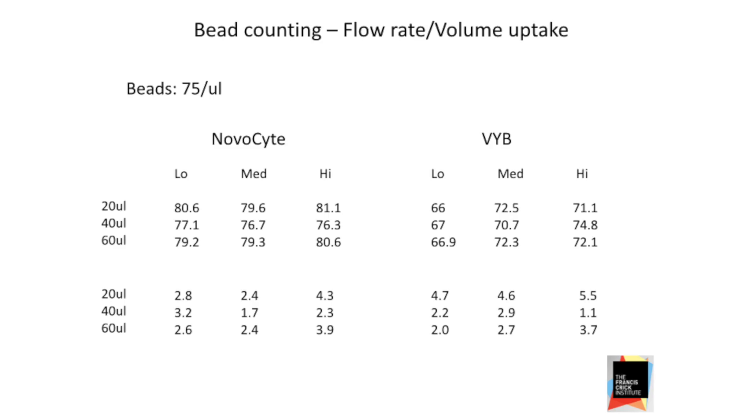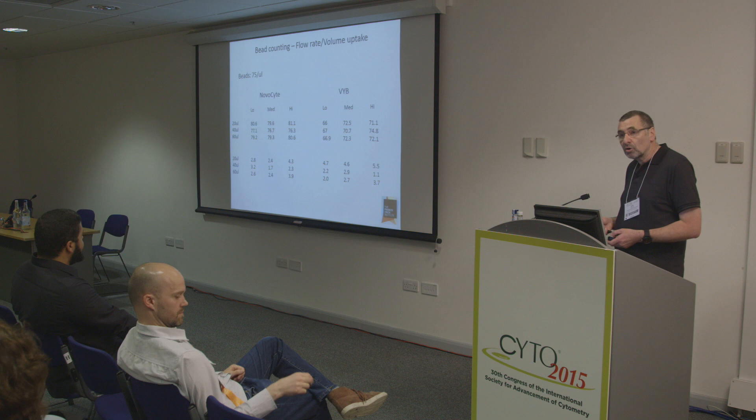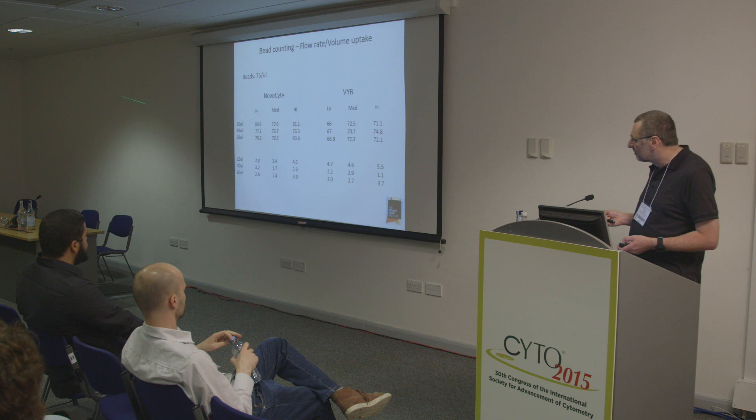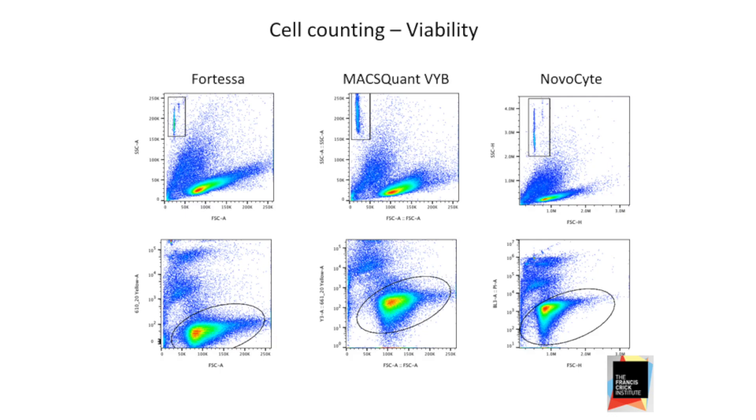We tried to distill a lot of experiments into something relatively simple. It shows that both volumetric machines — the NovoCyte and the VYB — have three different pressures, cunningly called low, medium, and high, which apply more pressure to the syringe so things run through more quickly. Because it's volumetric, we can tell the software how many microlitres we want to take up. We looked at a variety of different volumetric uptakes and different speeds, and showed that variability in the counting isn't bad and reproducibility across all conditions is very good.